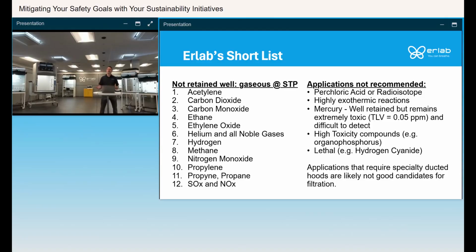And then any applications that you would need a specialty ducted fume hood for, such as a perchloric acid hood. You need a wash down hood so you don't have explosive crystals. A radioisotope hood has to be specially lined to protect against radiation. And then anything that's immediately lethal or extremely toxic. Mercury, although well retained, is extremely toxic and it's difficult to detect breakthrough. And anything, if you have an SDS of anything that says fatal if inhaled, we're not going to recommend you use that in our ductless fume hoods.